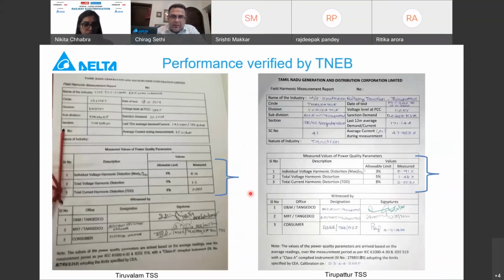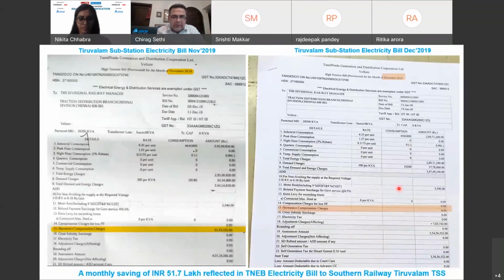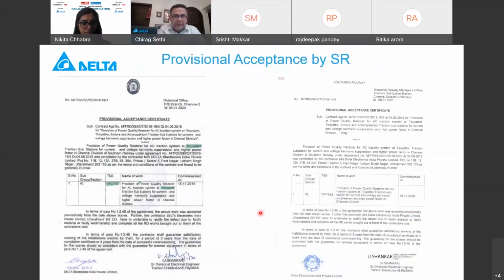This I call our report card. The Tamil Nadu Electricity Board also verified our system performance. From a TDD limit of 8%, what was observed during measurement was a maximum of 2%. That is how Southern Railway got the benefit of mitigation and waiver of their ongoing penalty. You can see here the earlier bill, where there was a harmonic compensation component, a penalty of 51 lakh rupees. In the month we commissioned our equipment and it got verified, this compensation was waived off. So almost 50 lakh rupees of benefit every month for every TSS. This is our acceptance.